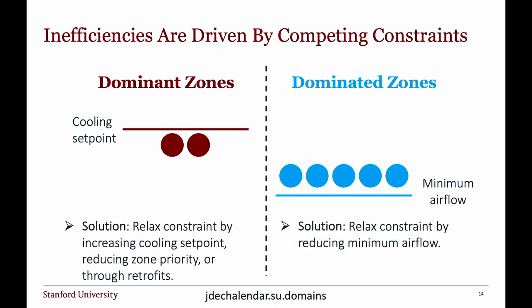For the dominated zones, there's a lot of research pointing to too much ventilation in these spaces, because parameters like humidity, temperature, and ventilation are set very conservatively, based on rules of thumb. They're conservative for good reason, since in many cases we don't have measurement. But if we have measurement, we can relax those constraints and make them more specific.